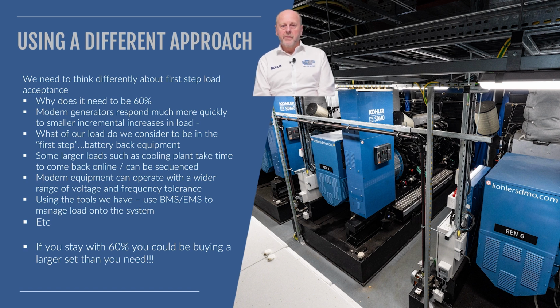These gains mostly come from improvements in engine performance, getting more power from the engine. Smaller engine capacity for a given power output is then linked with smaller rotating mass, hence lower inertia, and this can have a direct impact on the dynamic performance of the set, particularly on first step load acceptance. So there is a new balance that needs to be struck here. We need to weigh the benefits of lower fuel consumption and emissions versus the potential reduction in dynamic performance.